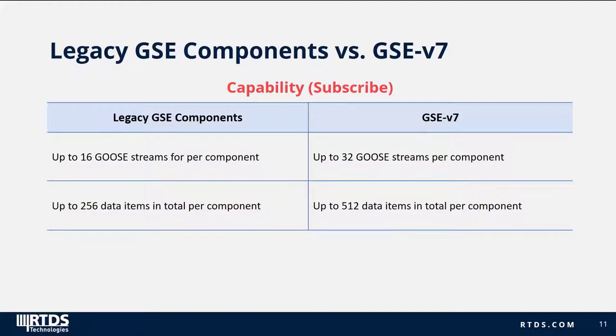When considering subscribing capabilities, the legacy GSE component can subscribe to up to 16 GOOSE streams per component, whereas GSE V7 can subscribe to up to 32 GOOSE streams per component. Similarly, the legacy GSE component can subscribe to up to 256 data items in total per component, whereas GSE V7 can subscribe to up to 512 data items in total per component.